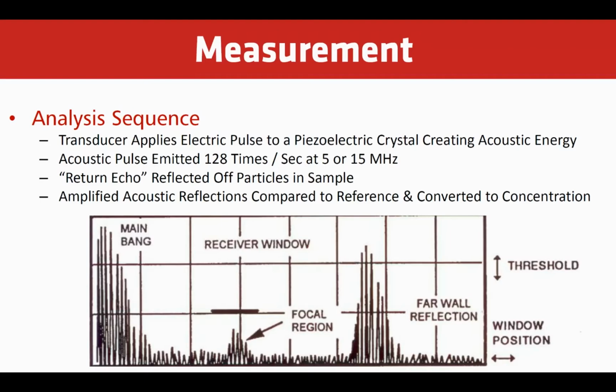So what happens is we have a calibration table that it looks at, and depending on the amount of counts we have come back, it looks it up on the table and will output that as the calculated ppm value of either suspended solids or oil in water.